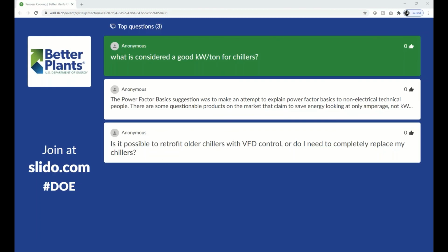But for our chillers and our facilities, we are running them all year round, right? For winter and fall, when the wet bulb is pretty good, our actual kW per ton will be a lot less than that. So the annual average kW per ton for your facility, if we can get somewhere around 0.3 or 0.4, I think that's going to be good.